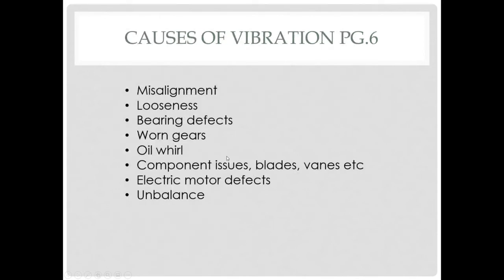There are different causes of vibration: misalignment, looseness, bearing defects, worn gears, oil whirl, component issues such as bent or cracked blades, bad mounting, motor defects, and general shaft unbalances. Using frequency, we can narrow down our suspect area in terms of analysis. You'll see later how we can use frequency to kind of point us in the right direction as to what kind of symptoms we're dealing with.